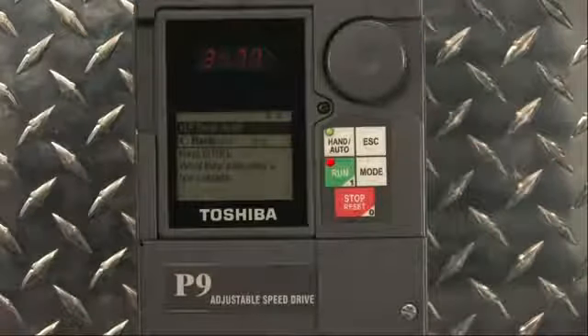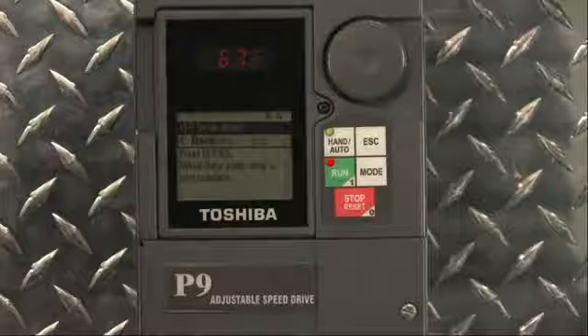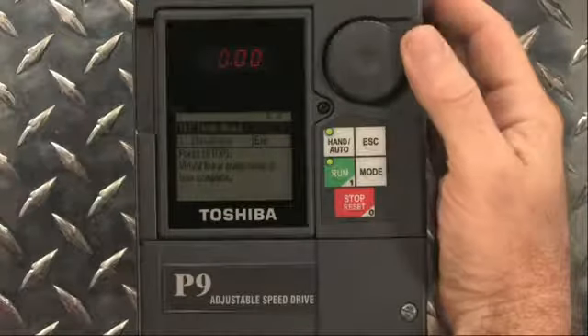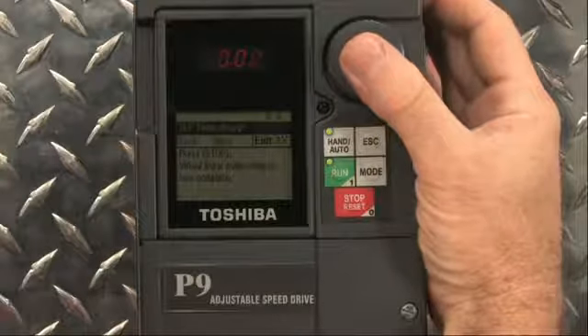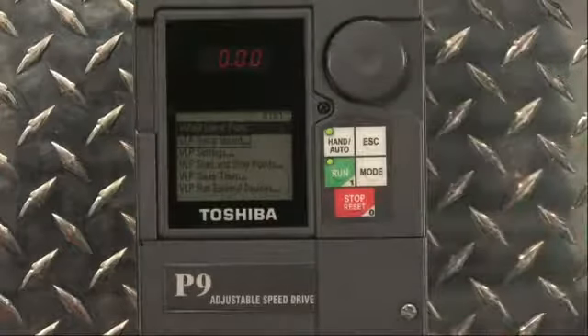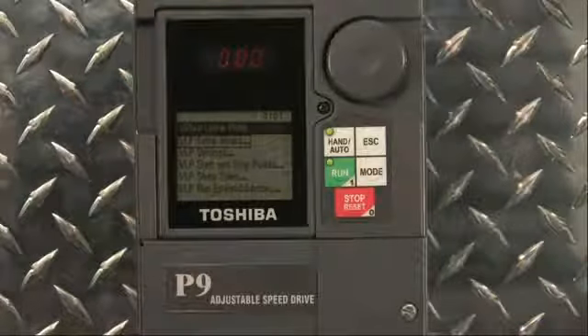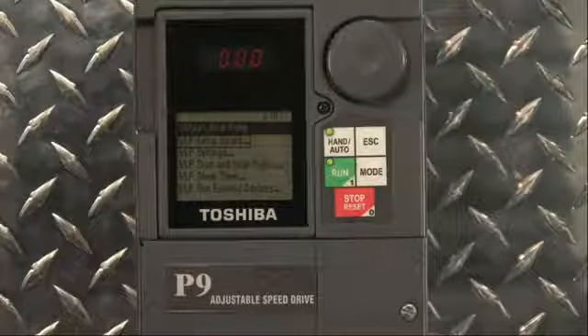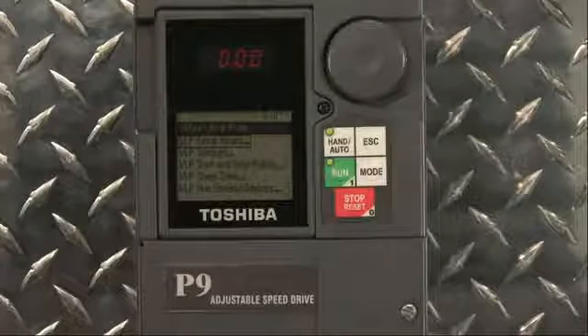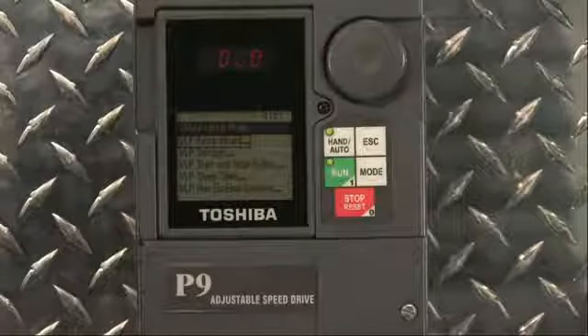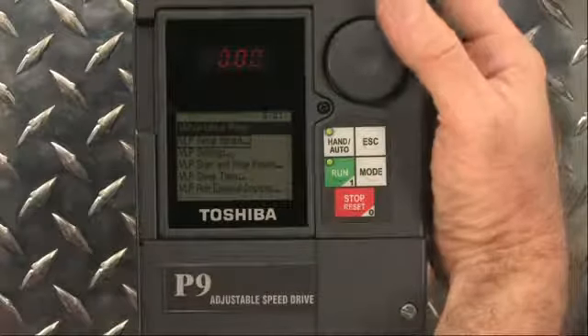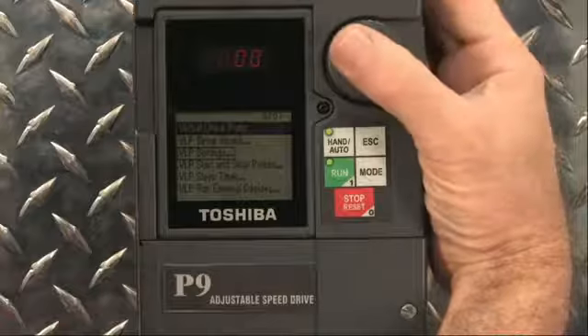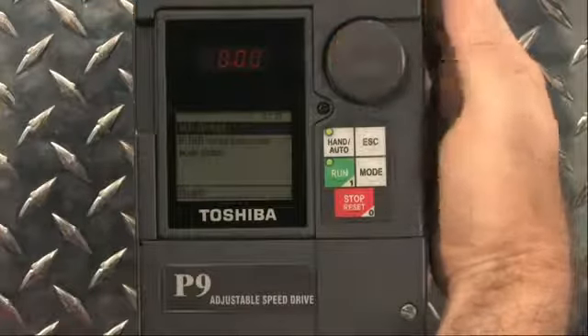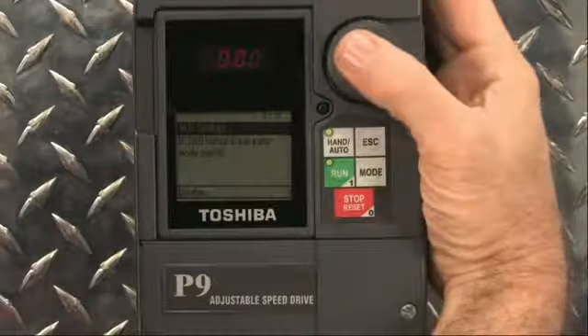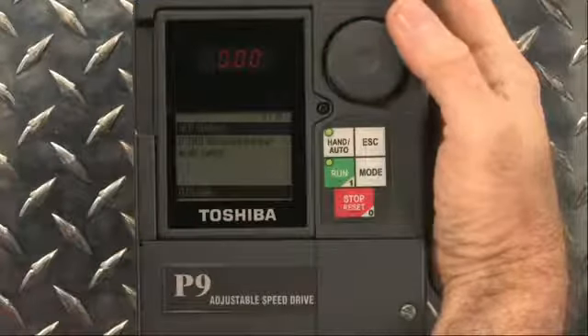The next screen instructs the operator to press Stop and states that the setup is now complete. Once the pump comes to a complete stop, the Exit option becomes available. In order to save all of the data just entered, Exit must be selected. The last step to commission this pumping system is to simply enable the VLP process. To do this, we need to re-enter the program menu and the Virtual Linear Pump submenu. Under this submenu, select VLP settings. Notice how the first parameter, Virtual Linear Pump Mode Switch, is disabled.